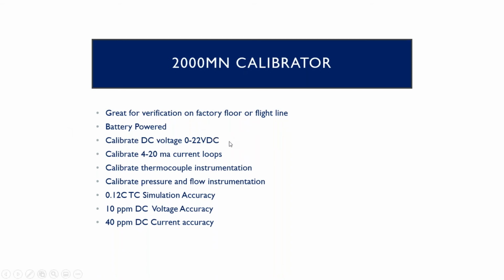We output 0 to 22 volts DC, so it's good for calibrating meters on the low range very accurately, that is our forte. It also outputs 4 to 20 milliamp for monitoring current loops, and it emulates thermocouples. This confuses a lot of people, some people use temperature baths for calibrating thermocouples, but we don't calibrate the thermocouple itself, we emulate it. We put out a voltage that looks like it's from a thermocouple, and use it to drive your instrumentation, and that's how you calibrate your instrumentation.